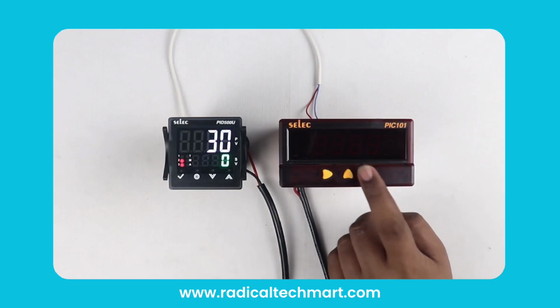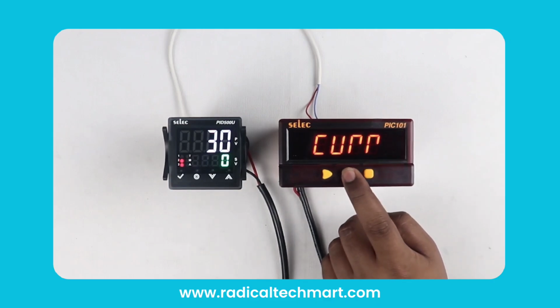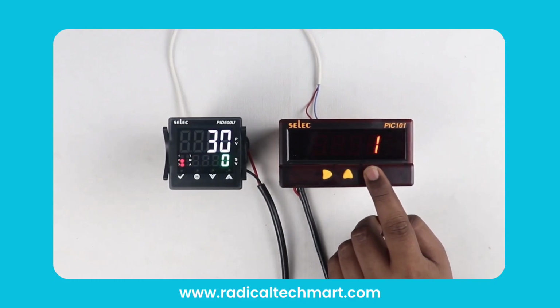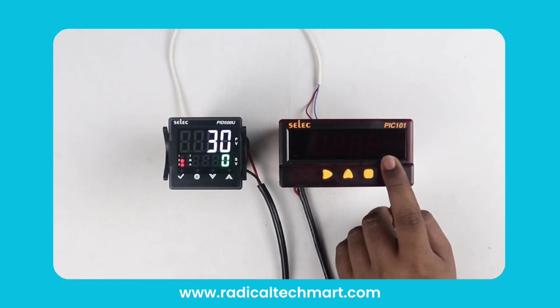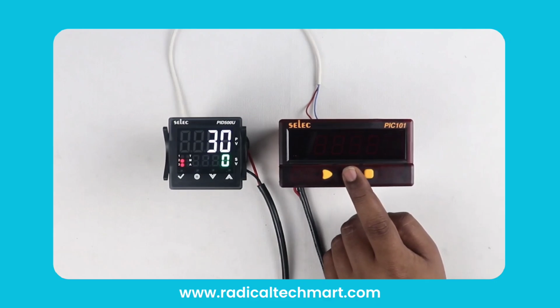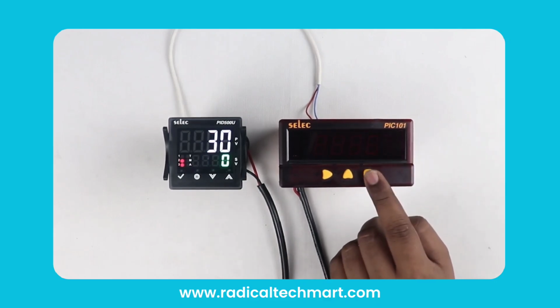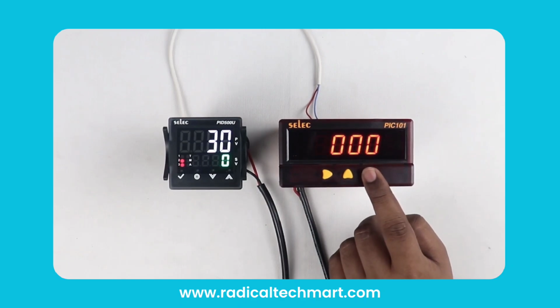The next step is input selection. Here you can choose your input type such as current, volt, J-type, or K-type using the middle key. After selecting, press the square key again to see the resolution. You can adjust the resolution to see the process value point by pressing the middle key.